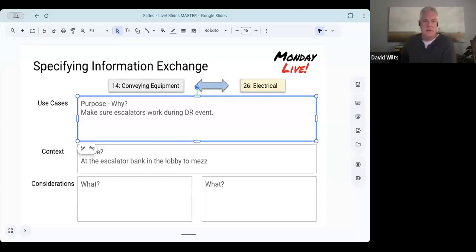May I interject, please? Absolutely. Usually it's an operations decision which lifts get power during a demand response event. Usually elevators have to be kept running for fire and life safety. But where this really comes into play is during a blackout situation when you switch over to running on generators. When you're running on generators, you obviously can't power every lift, and you have to be very strategic about which lifts are powered to enable firefighters to rescue people and evacuate people and things like that.